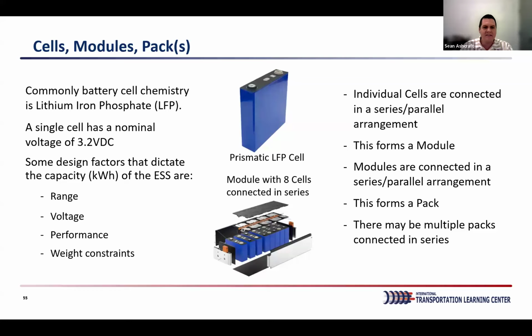Here in the middle of the slide is a single prismatic LFP cell, enclosed in an aluminum enclosure. Right below it is a module. Inside this module, for example, there are 8 cells connected in series. These modules get connected in series or parallel arrangement, building up what is known as a pack. Again, depending on the OEM, there may be multiple packs connected in series to make the energy storage system.